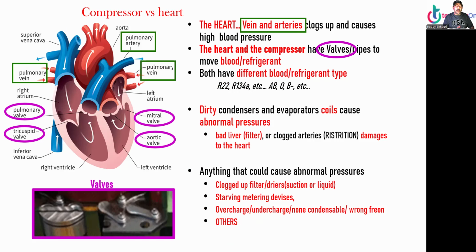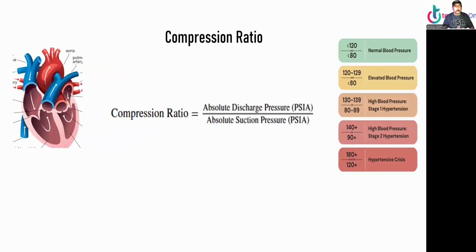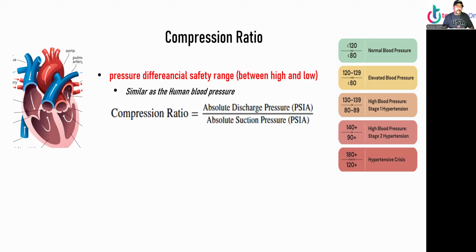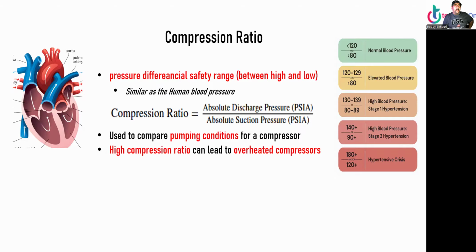All right, so it makes sense how the compressor and the heart are very similar, except one is a vapor pump and one is a liquid pump. Now, compression ratio. It's a pressure differential safety range between high and low, similar to human blood pressure. It's used to compare the pumping condition for a compressor. High compression ratio can lead to an overheated compressor. Alrighty, compression ratio is the absolute discharge pressure divided by absolute suction pressure.